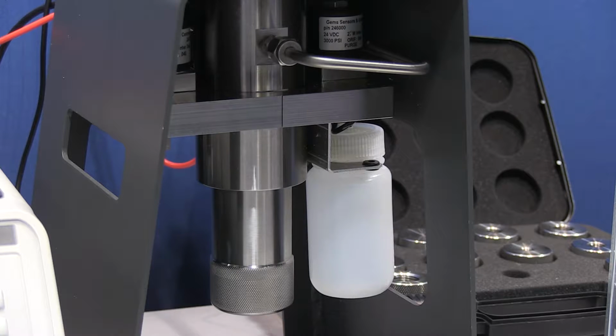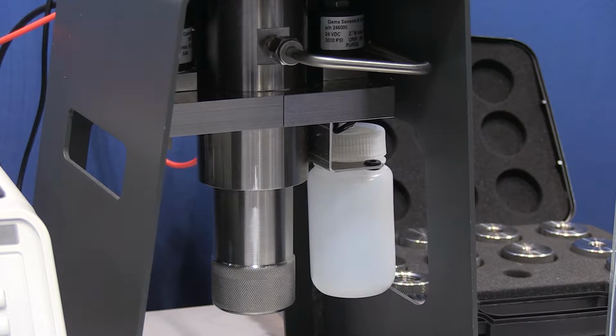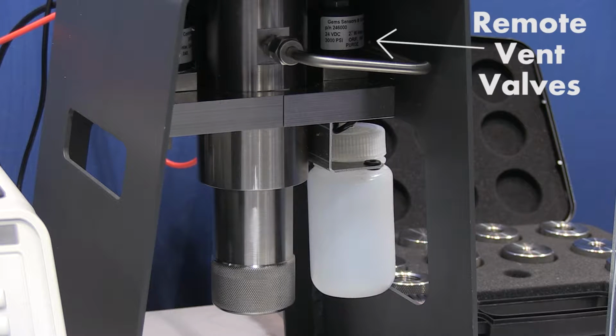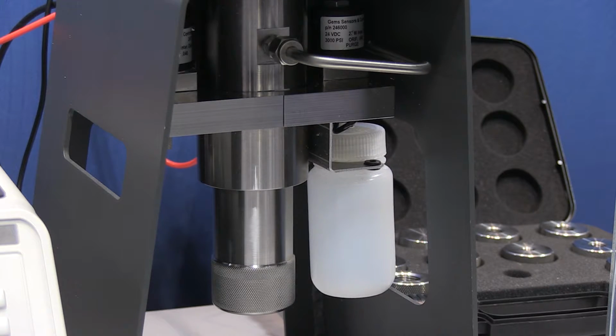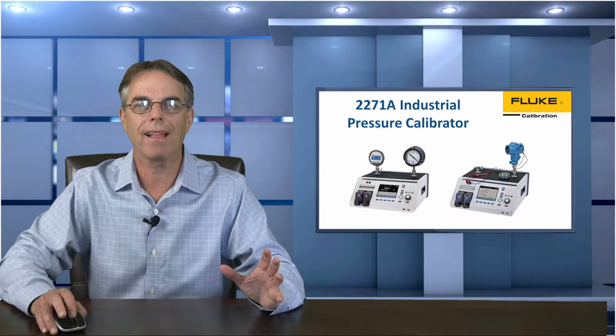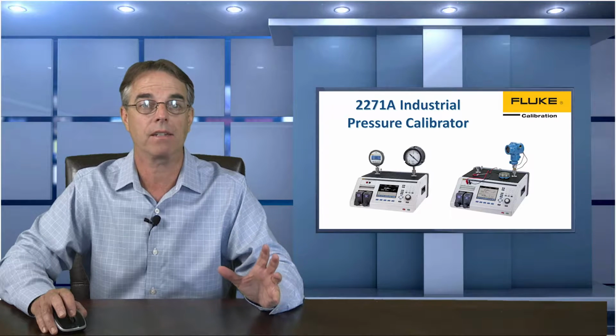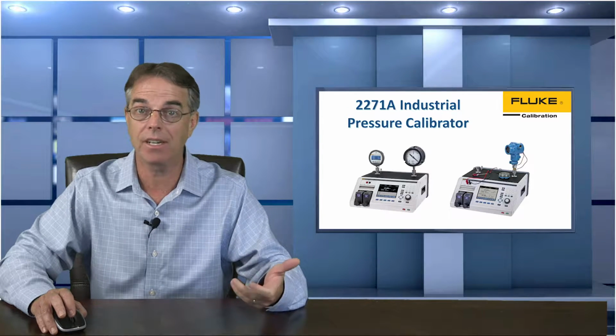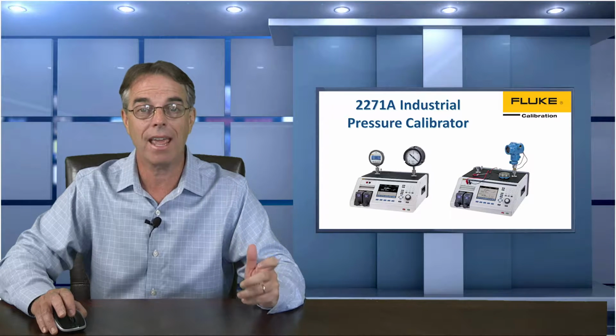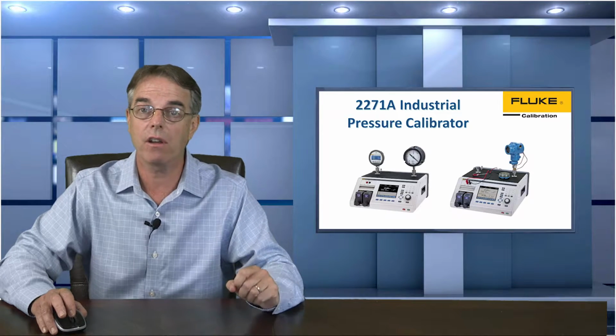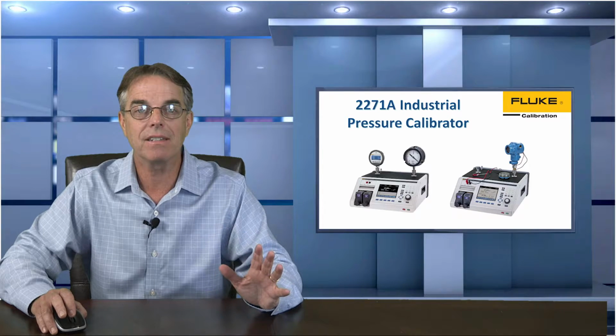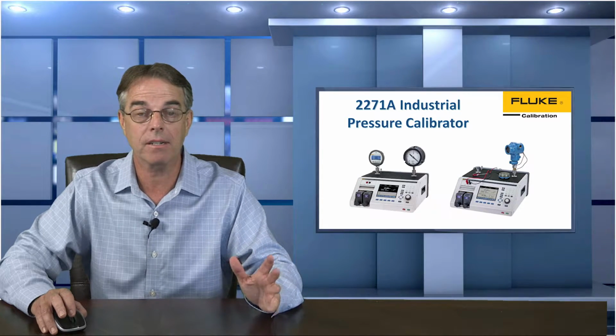So when you're increasing pressure, it works absolutely normally like it does without CPS, but when you decrease pressure, you'll hear some clicks. And what it's doing is venting the pressure remotely from the calibrator itself. So in this case, flow again is away from the calibrator and into and through the CPS assembly. What I like about this product is the way Fluke Calibration is building more functionality into one box, even eliminating the need for pressure tubing and adapters and Teflon tape, even by having those hand-tight quick connectors on the top. No need for a multimeter if you're doing simple voltage or current or even HART outputs on your transmitters. It simplifies the setup for the calibration technician and takes up less bench space, which is nice.